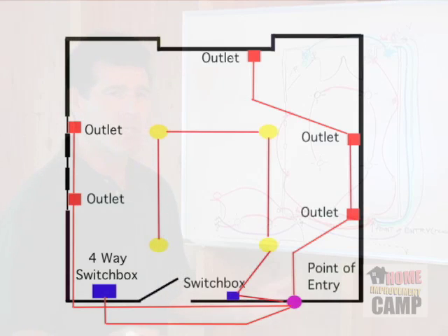An arc fault circuit interrupter is basically a circuit breaker on steroids. It's just a circuit breaker that goes in the circuit breaker box, and it monitors the neutral as well as the hot. A regular circuit breaker just tells you if you're drawing too much current on the hot leg. An arc fault circuit interrupter measures the amount of electricity going through the neutral and through the hot wire.